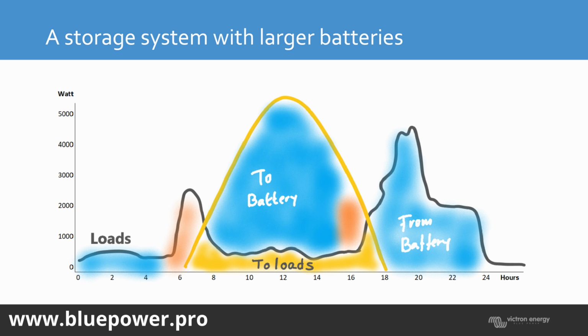So depending on the battery size that you design in your system, you can almost run completely optimized with your solar system if you've got enough PV. So you can achieve that majority of your PV excess power goes to your battery bank, which is sufficiently sized to take all that PV, and at night you run completely off PV. Maybe some peak loads get covered from the grid.